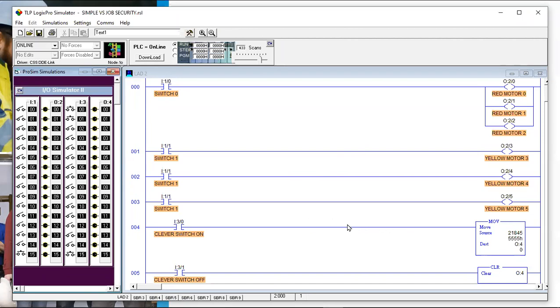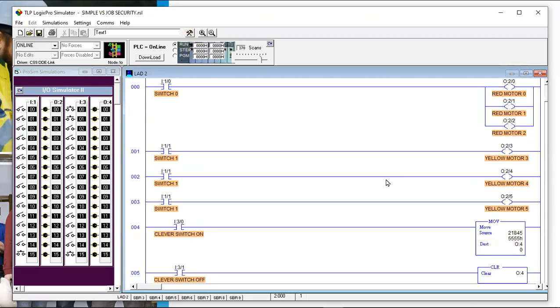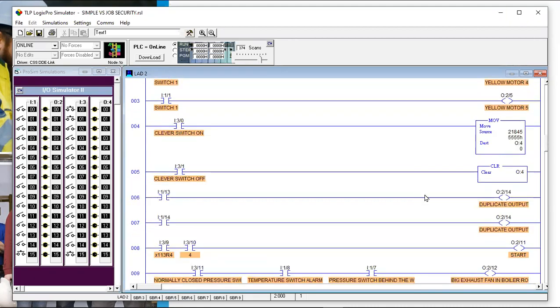Now let's look at other mistakes you can make. Here's one — we're going over do's and don'ts. This next example is a definite don't — something you just can't do. What we have here are what are referred to as duplicate output bits. We're trying to turn something on, and here's output 2-1-4, and here's another output 2-1-4.